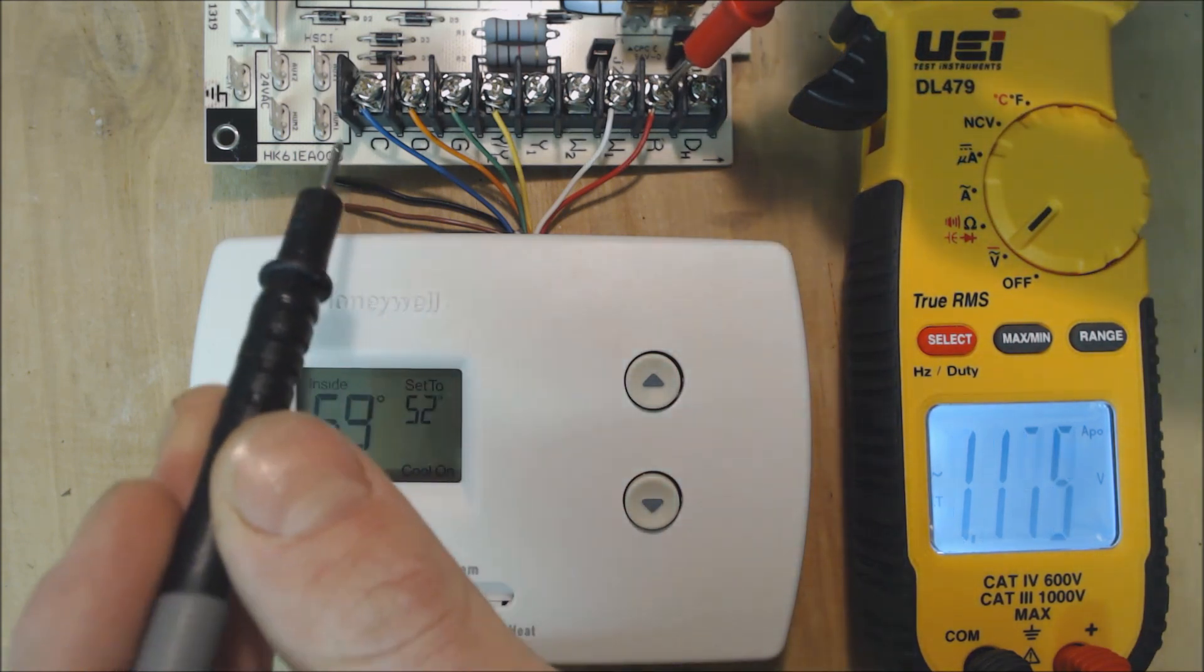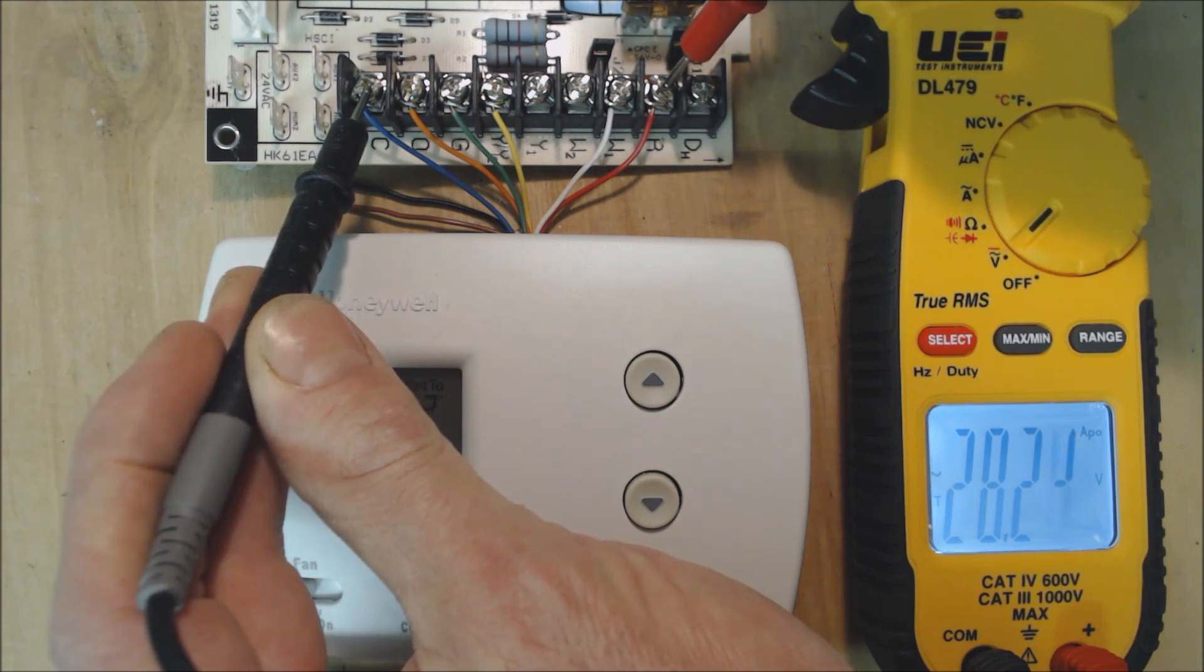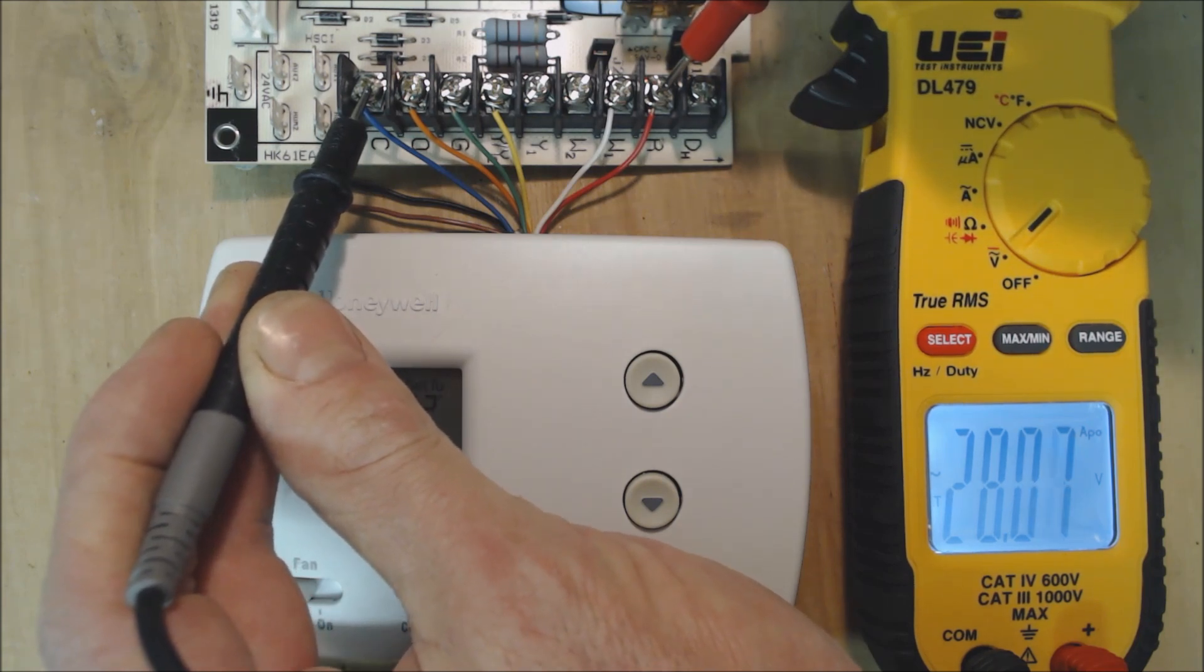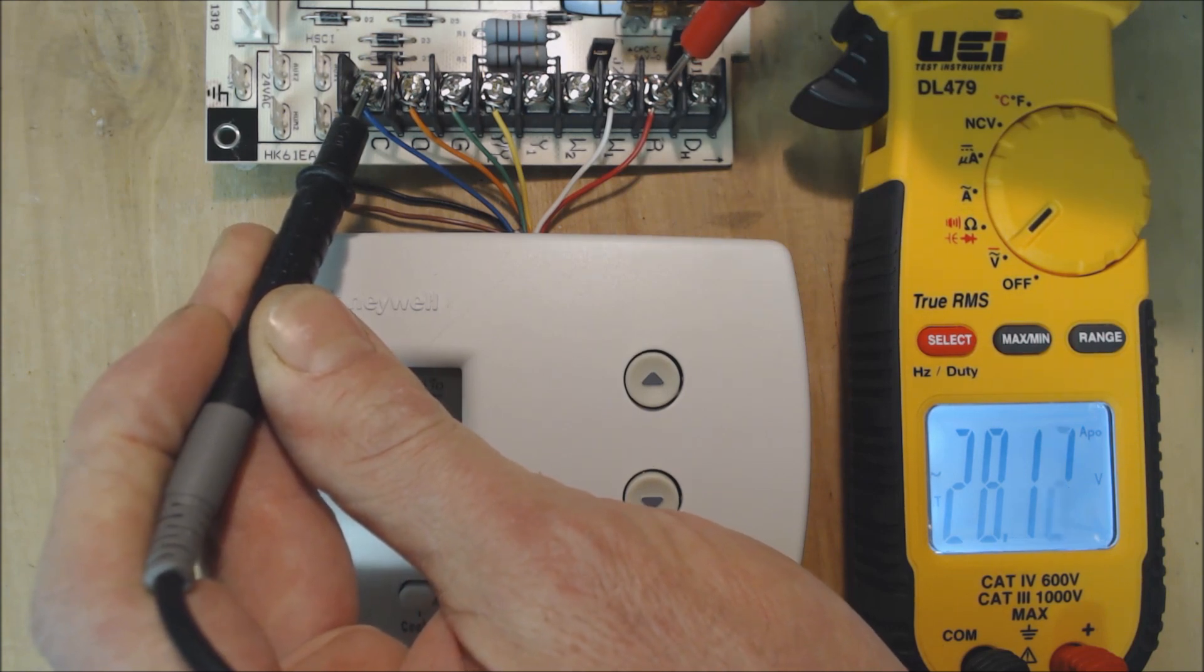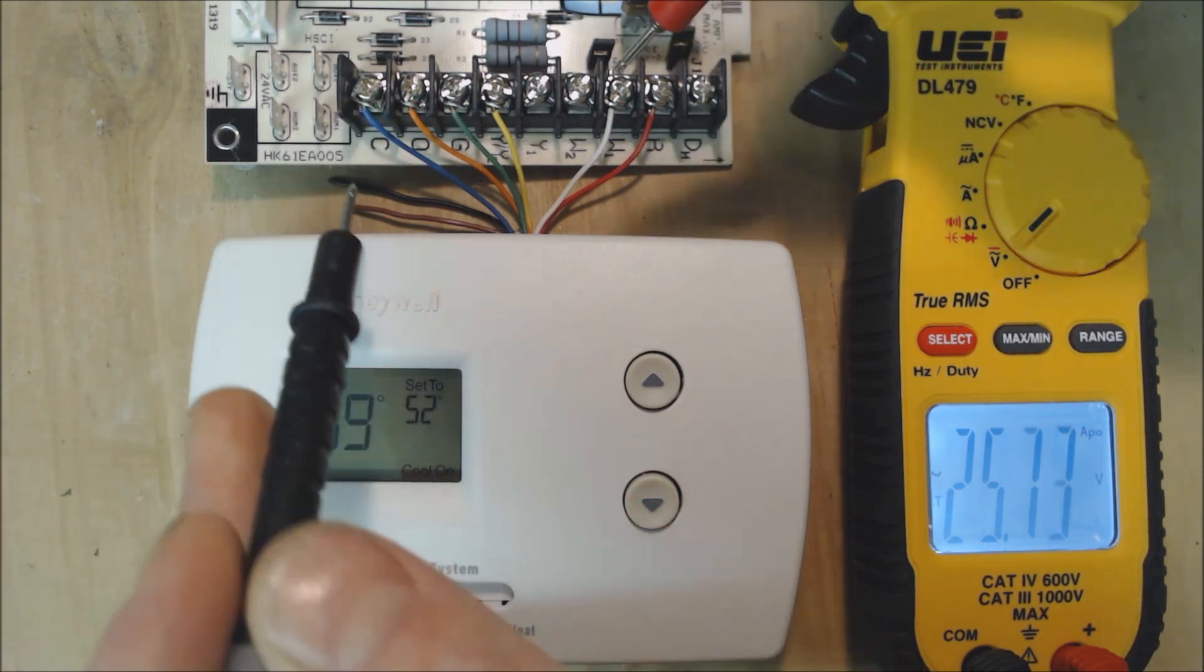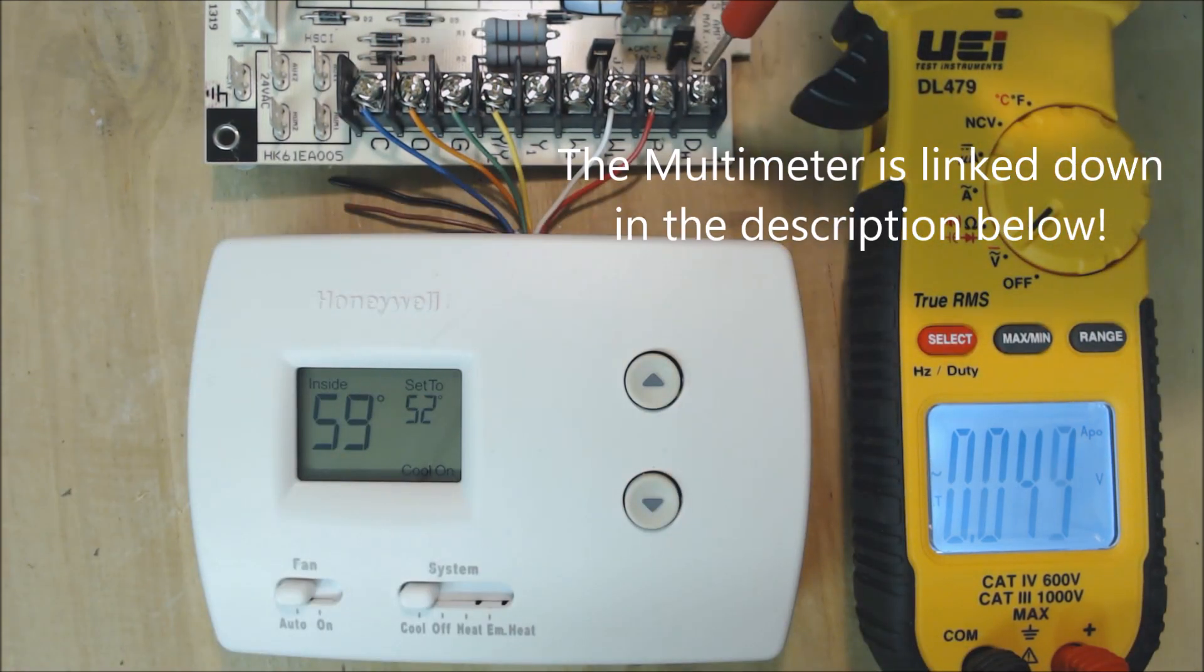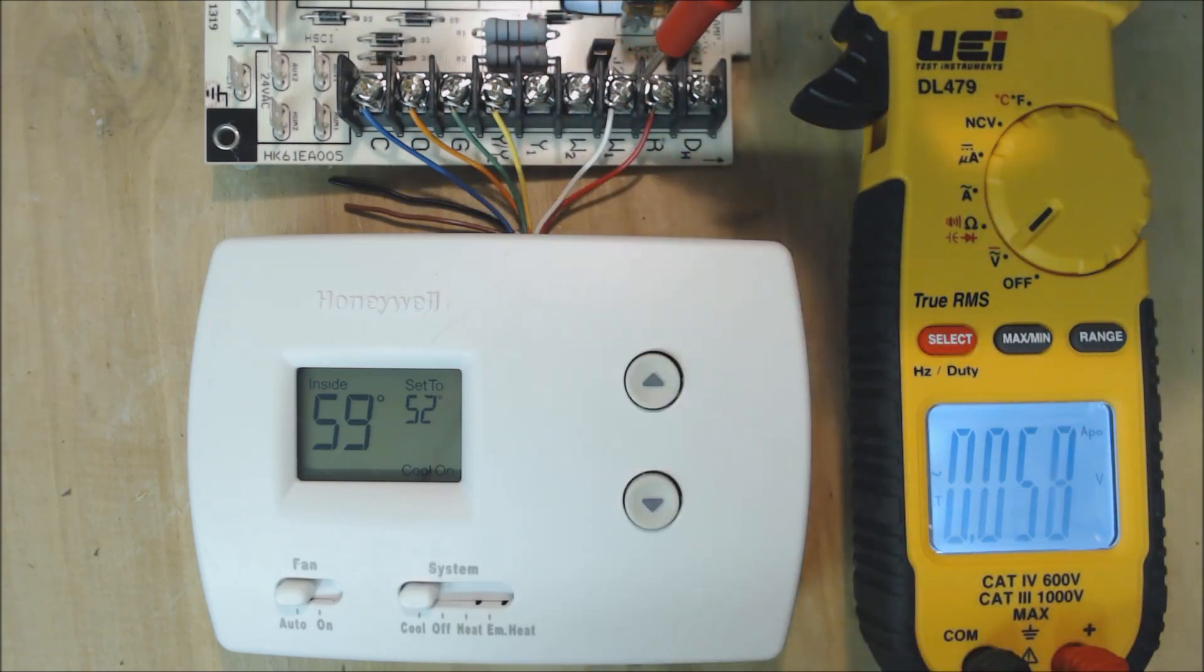We always have 24 volts in the control board between R and common. You see we have 28 volts right there. Anytime you have a good power supply, you're going to have anywhere from 24 to 29 volts. Presently we have 28.1 volts. We can verify that we're sending voltage to the thermostat by reading the indoor air handler's control board.